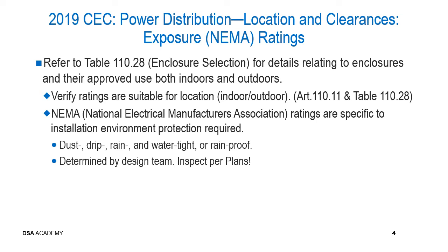Project inspectors must verify that the ratings are suitable for the location, generally indoors and outdoors, and additional information is also provided in Article 110.11. The National Electrical Manufacturers Association, also known as NEMA, provides ratings that are specific to installation environmental protection that is required for the equipment. And the different criteria for protection of the equipment are dust, drip, rain, and water tightness, or rain proof. Obviously, these particular environmental protections are going to be determined and approved by the design team, and it's extremely important that the project inspector inspects the installation of these components based on the information that was provided by the design team in the approved plans.